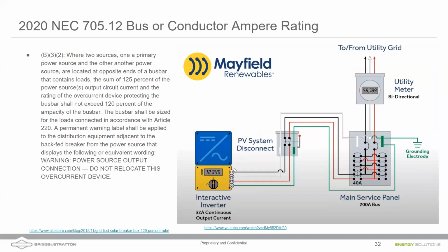This is much more common. This is what we see a lot in the industry now. We still have a 200 amp bus and a 200 amp main breaker that's not called out there. When you have 2 sources of power and you can locate that backfed breaker on the opposite end of the bus bar, the output current of that device should not exceed 120% of the ampacity of that bus bar. Essentially, you're allowed to exceed the ampacity of the bus bar as long as you locate that backfed breaker at the opposite end of where the main is coming from.